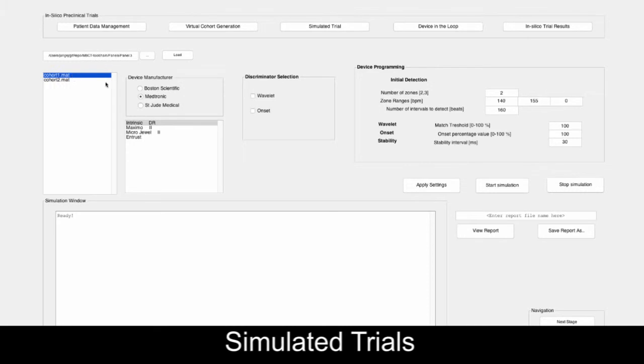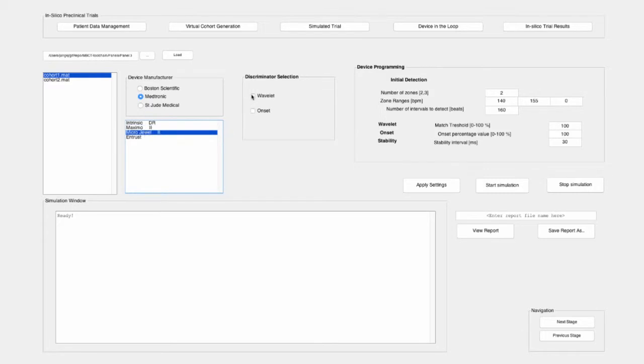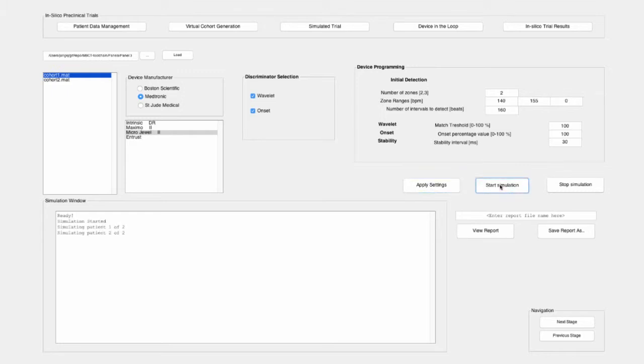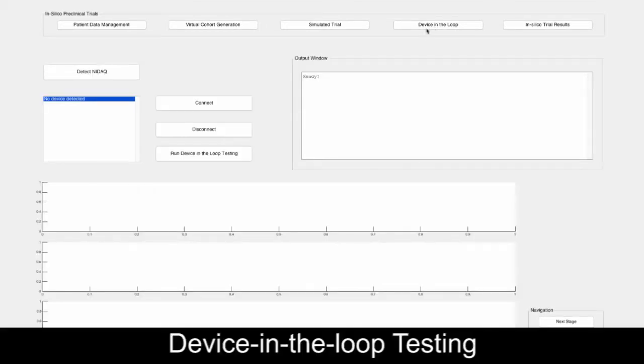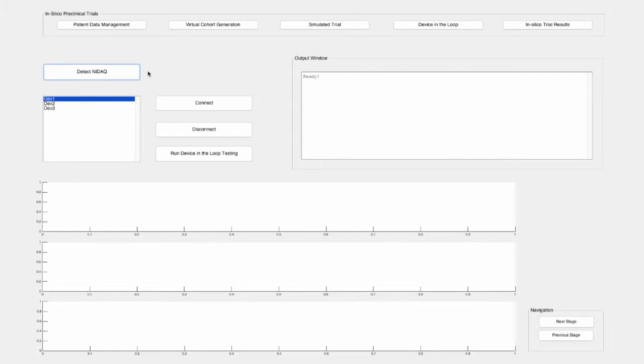To evaluate the performance of the device, the trial can be run on a range of implantable cardiac devices with different device settings. The simulation is executed for each virtual patient. In this example, our toolchain displays the progress of the simulation for a two-patient cohort. A result summary at the end of the simulation highlights the simulated trial results. In addition to device simulation, in-silico trials support testing with the device in the loop. At this stage, the user can feed a real device with the signals from the virtual cohort.